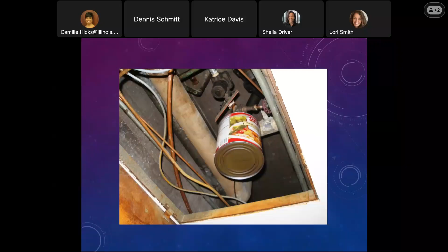Fires in resident rooms, smoke, and they wonder why. This is a unit on the exterior wall that runs the heating, sometimes the cooling through it, mostly the heating, the air fan units. But this was because one of the units in an adjacent room was smoking. Now they understand why, because look at all the debris. Nobody has checked these in years, and there's all kinds of debris in there, combustible debris that could cause a fire. So that is a deficiency.